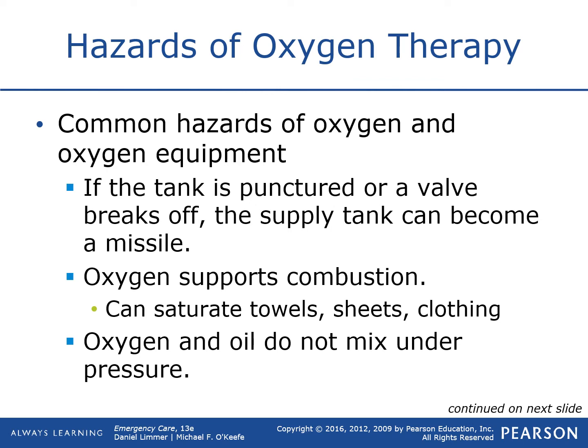And oxygen supports combustion, so that's why we are very adamant that you can't smoke or have open flame around it. And it can float around where we're delivering it. So if you're giving it to a patient through a mask, it will come out of the mask and then surround their face. It's going to surround the bedding that they're in. It might surround their clothes. And so you can have someone light a match at their feet, and since the oxygen has spilled out, it's going to be at the feet and combust up there and make its way all the way back up to the face. Also remember that oxygen and oil do not mix under pressure very well.